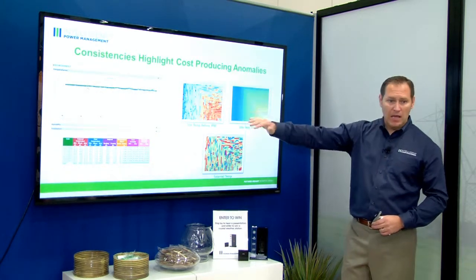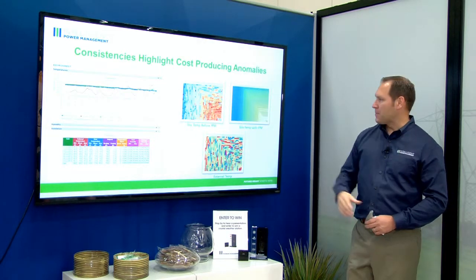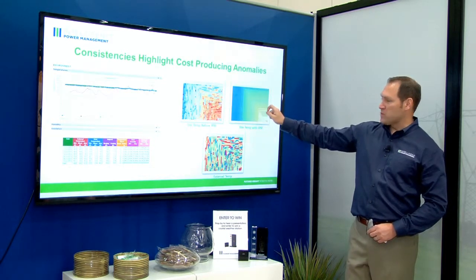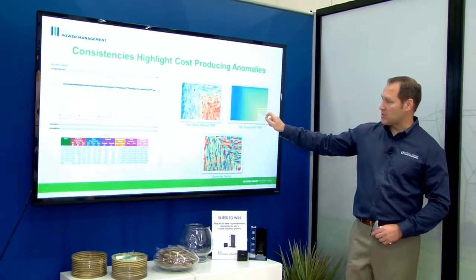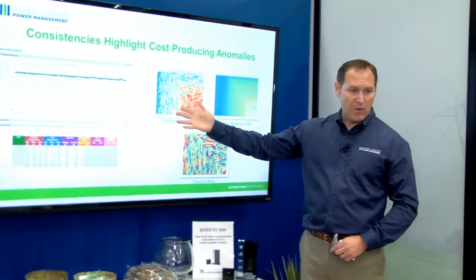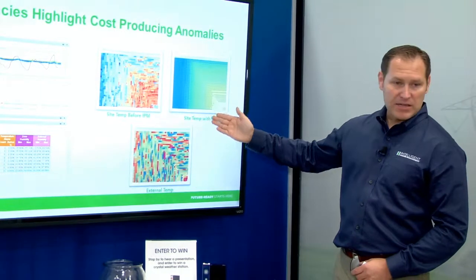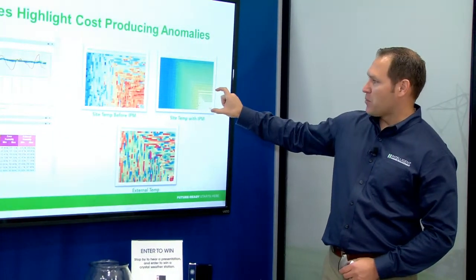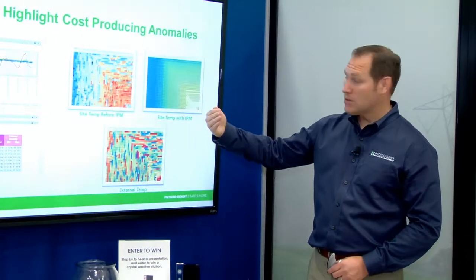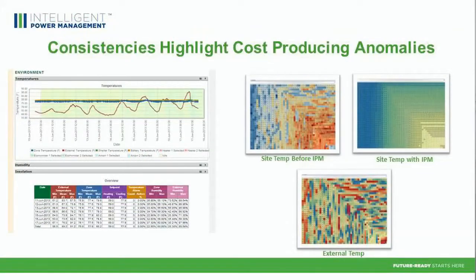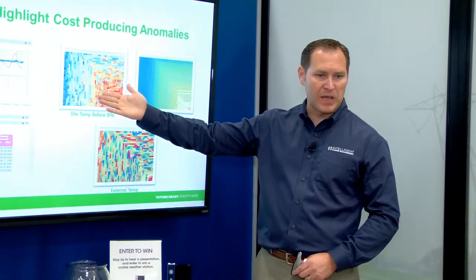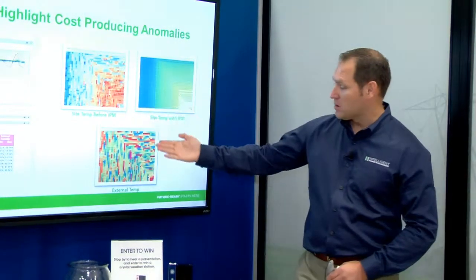Over here, it's taking the same data and putting it into a tree map or heat map format. Each block represents one hour block of time for this particular site — site temperature before and how it's being collected and run. Before: very inefficient, all over the map. After: very consistent. The bright red and orange means it's too hot; blue means it's cooler than nominal temperature; and the greenish yellow in the middle is nominal. If you look to the left — before — it's all over the map, very inconsistent, so you couldn't pick out anomalies based on this.